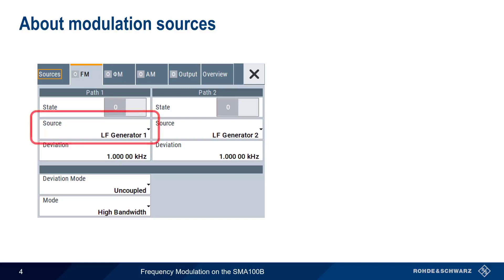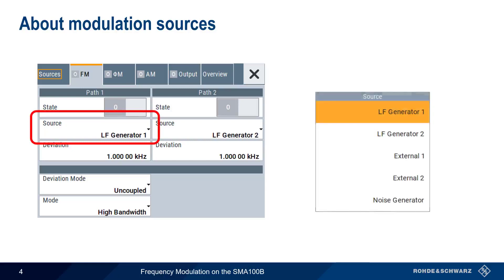A number of different modulation sources can be used with the SMA-100B. Some of these sources are internal to the instrument, and some are external. Internal sources of modulation include the two LF, or low-frequency generators, as well as the noise generator. We'll start by looking at internal FM modulation sources.